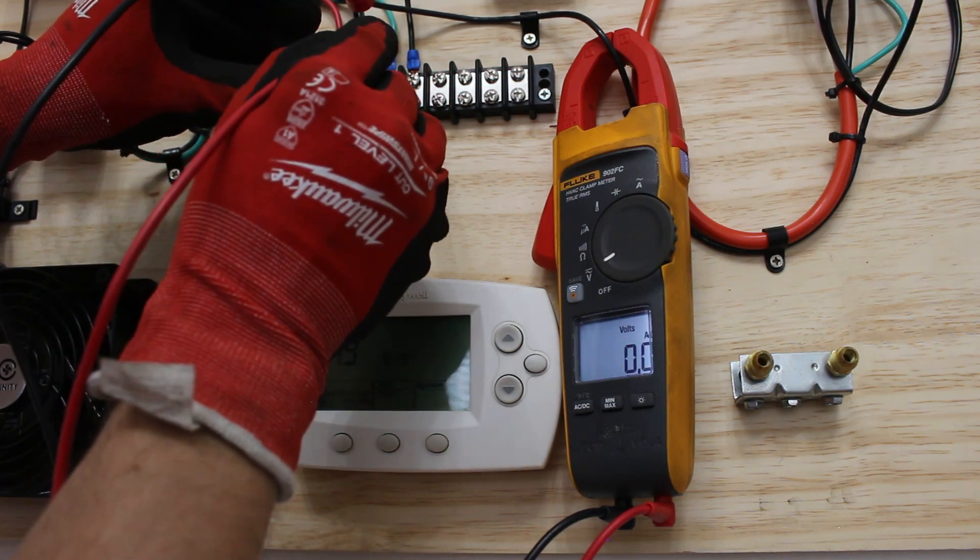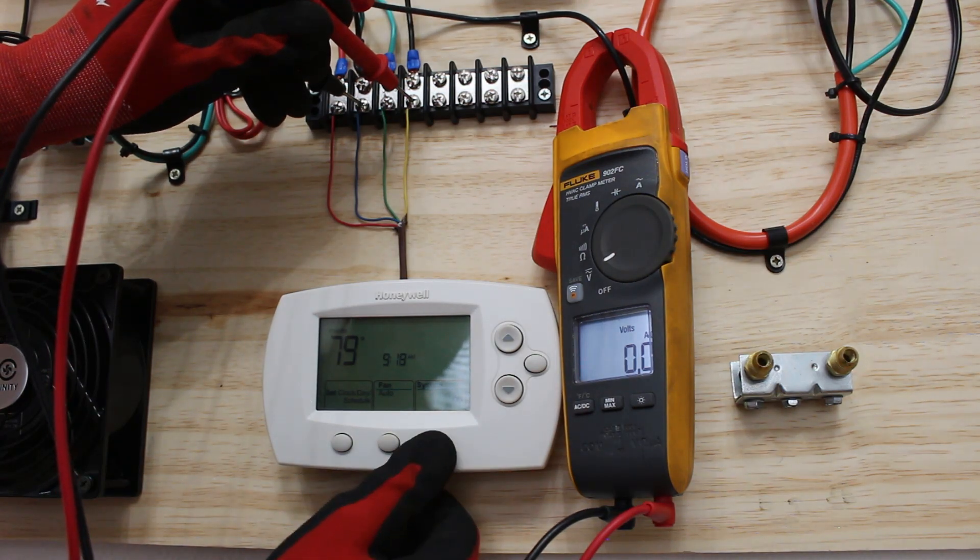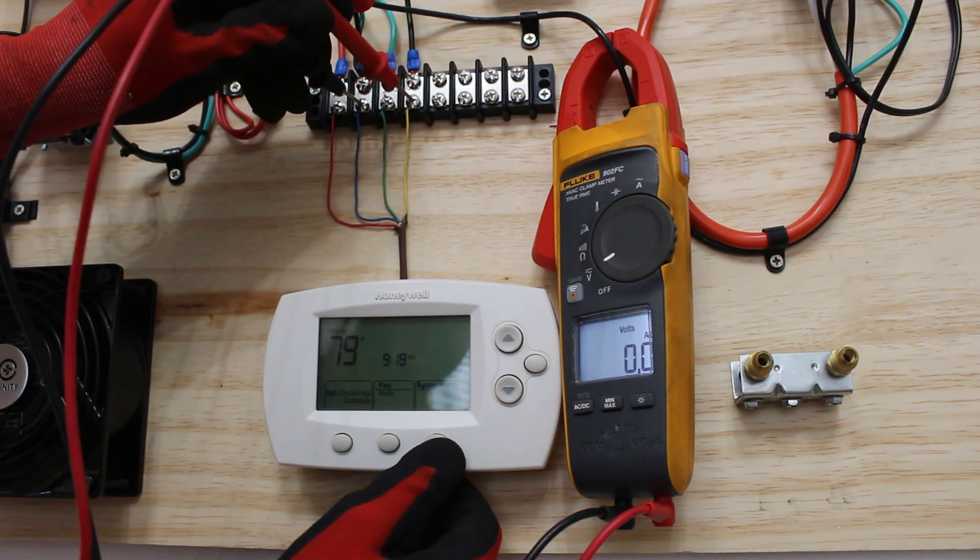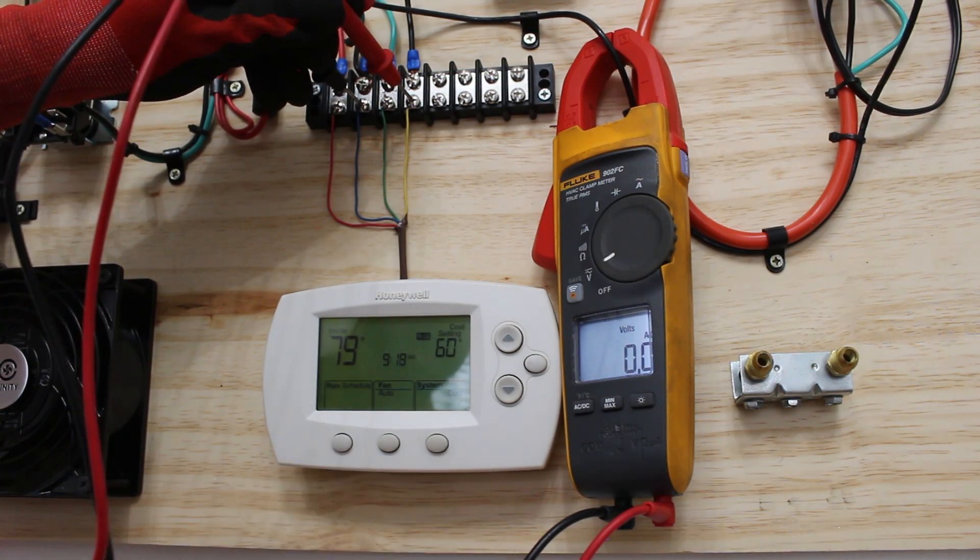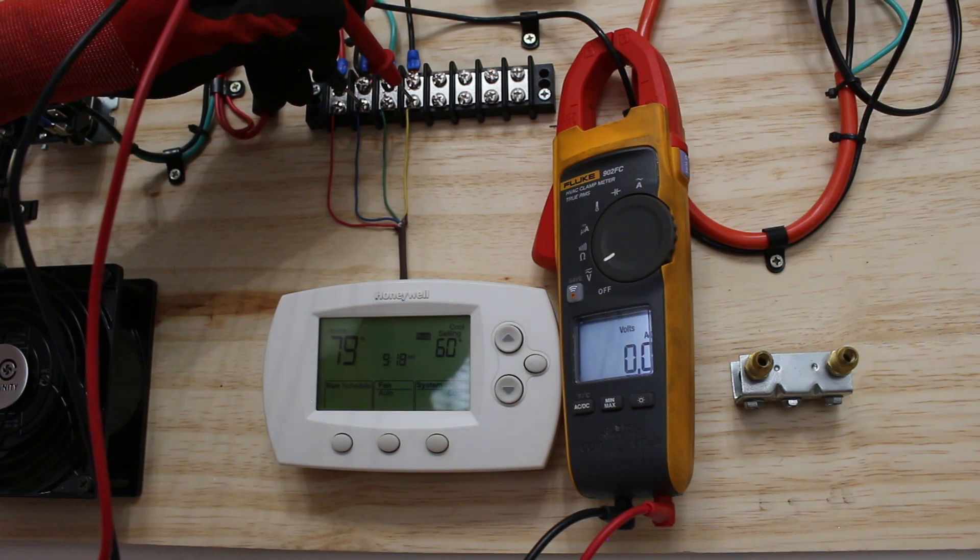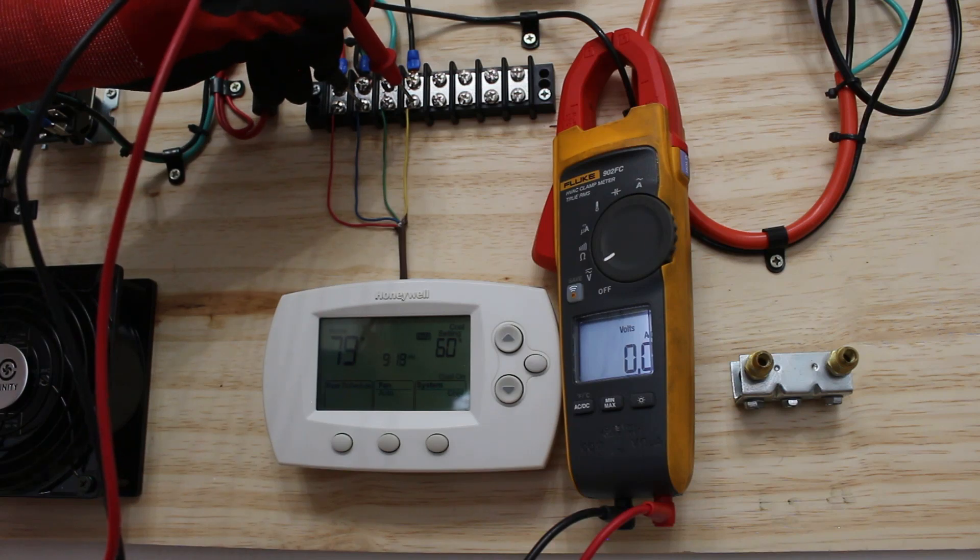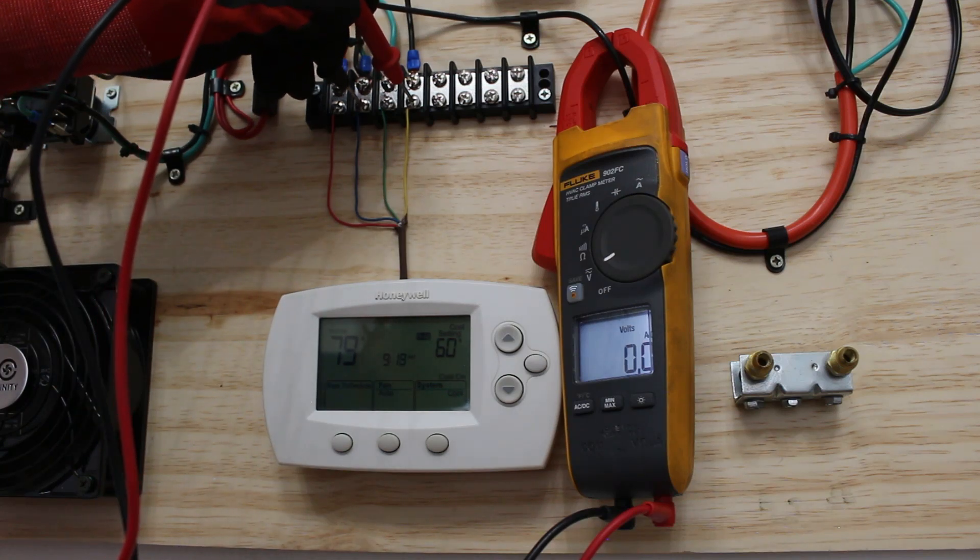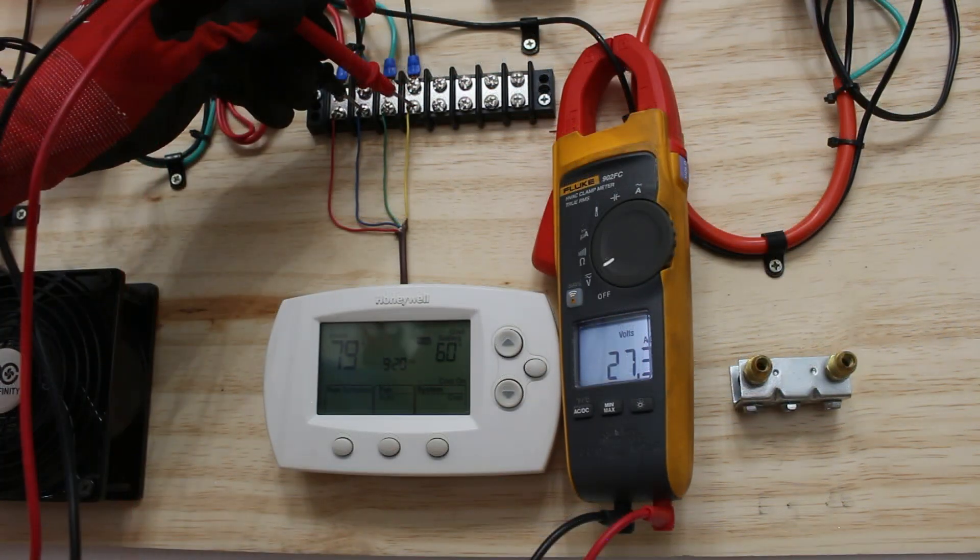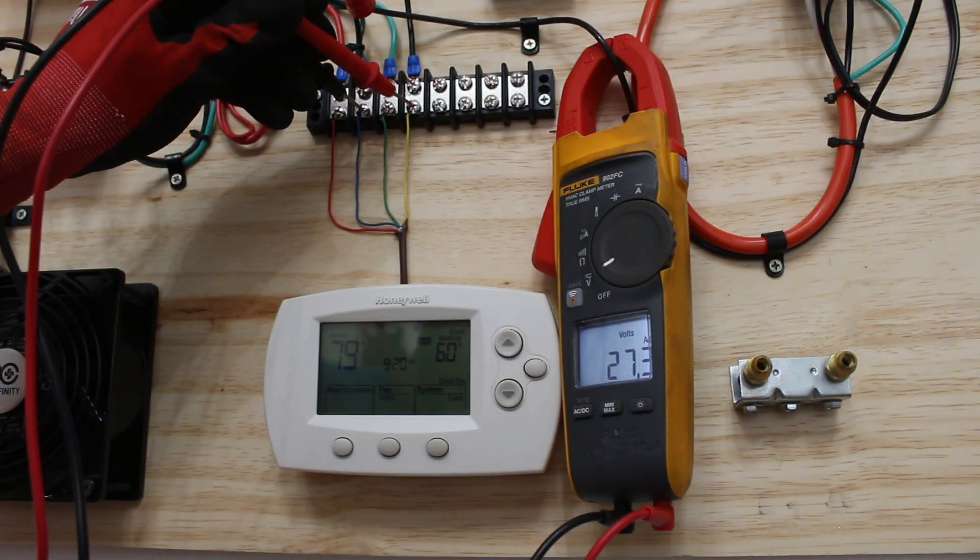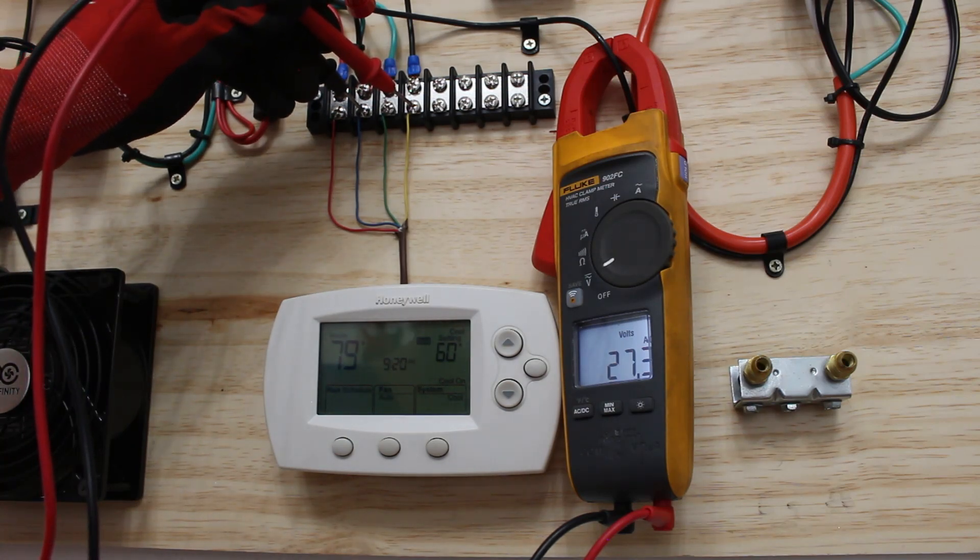Now we're going to go from common to cooling and let's see what happens on the Y wire. Right now we have between common and Y zero volts. If we put the system on cool, once again we have a delay. At the moment we have zero volts but once this kicks in between C and Y you will see there will be 24 volts. Our cooling operation has begun and as you can see between C and Y we now have voltage.